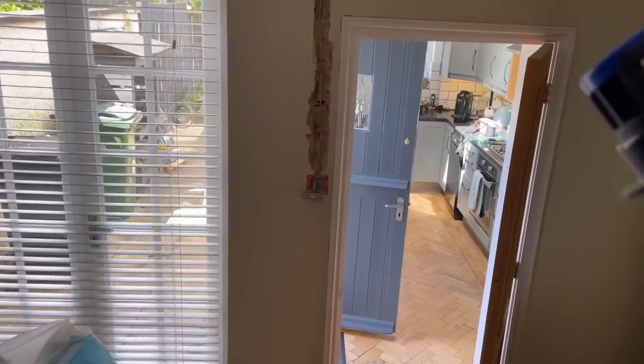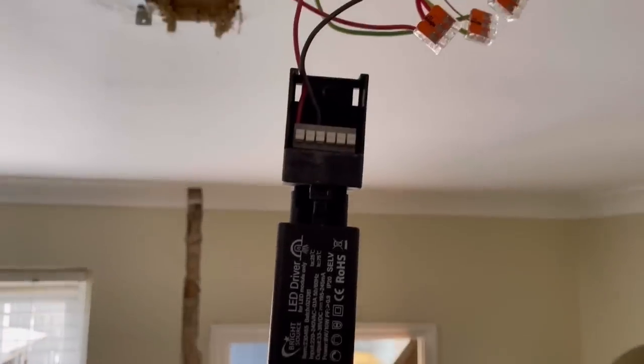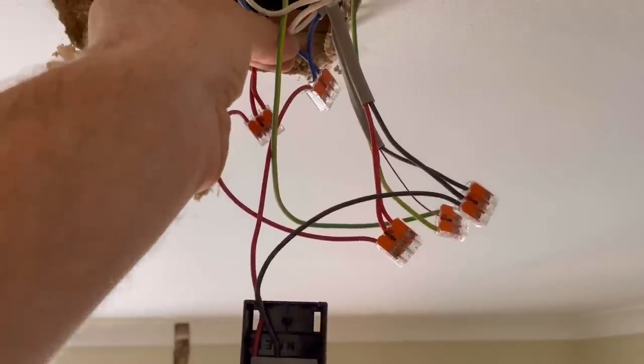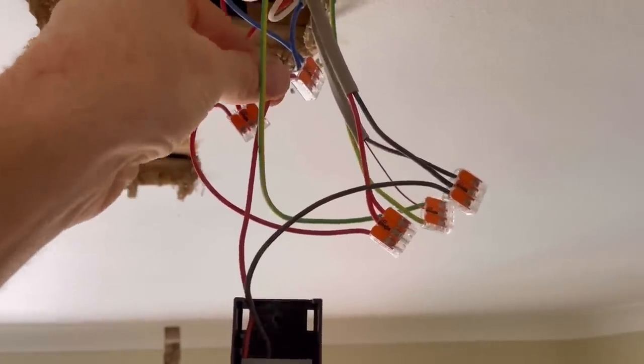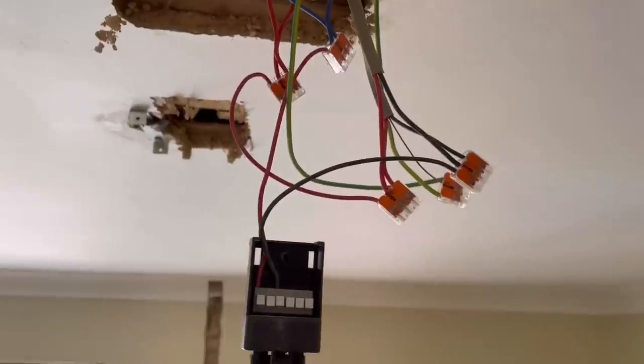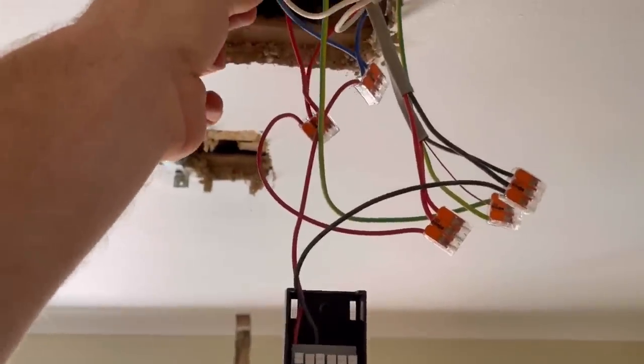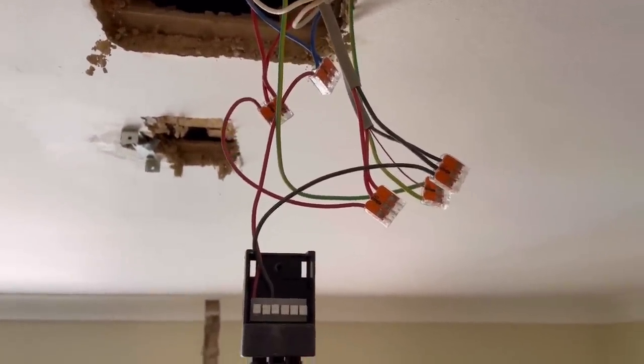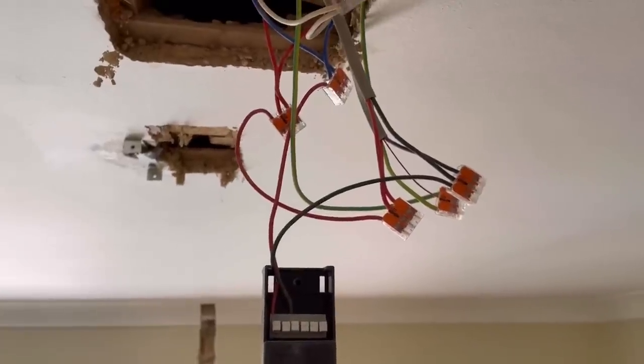And that's quite common with doing a normal two-way lighting circuit. And then on the other side, on the blue conductor which is still a live conductor, I've then took that one to the actual light fitting itself. What I'll do with this - because there's not a lot of cable - I'm gonna have to put this all in a joint box. I'll probably use one of the nice square Wago boxes, join it all up together and then just take a feed down to where the light is.